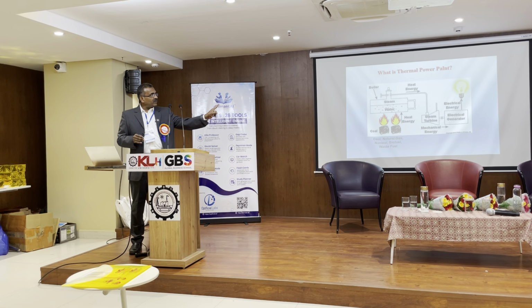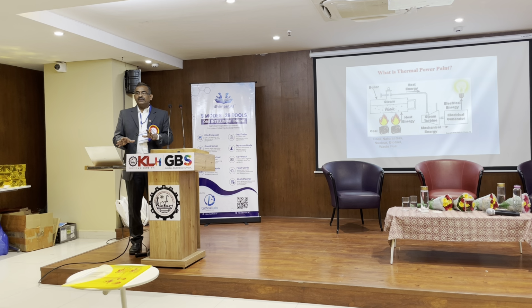In the generator, apart from taking care of the turbine, the electrical generator also needs great caution because it is rotating at, say for us, 50 Hz frequency. The allowed frequency range is 47.5 to 51.5. It has to stay within that range, otherwise if the frequency is disturbed we will have low voltage or high voltage problems, because whoever produces power, it finally goes to the grid, and all equipment connected to the grid gets disturbed. If we have high voltage, all equipment gets damaged. So we have to ensure the frequency stays within range.